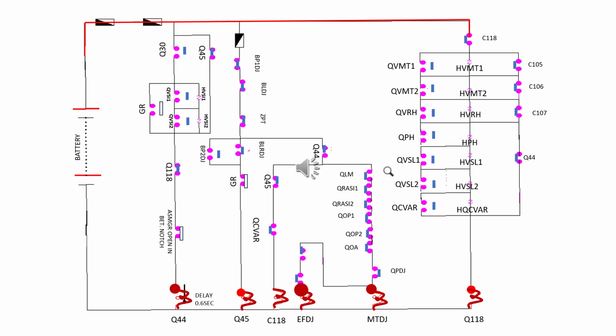Overcurrent, that means your traction transformer inside the loco is short circuit. It will draw high current from the 25 kV side. So this QLM will energize. There is a CT, just like our TRD system. When current will be more, the overcurrent relay will energize and trip the MTDJ, and the DJ will be open.